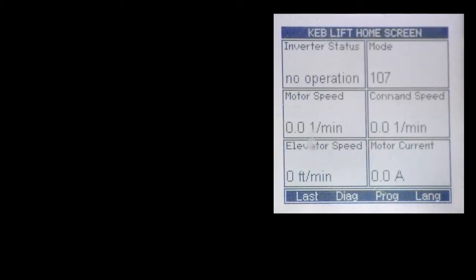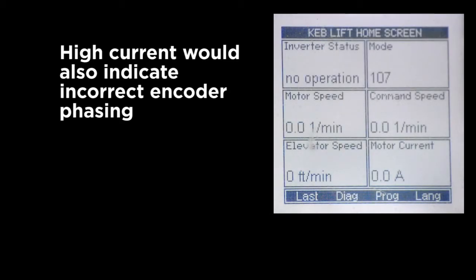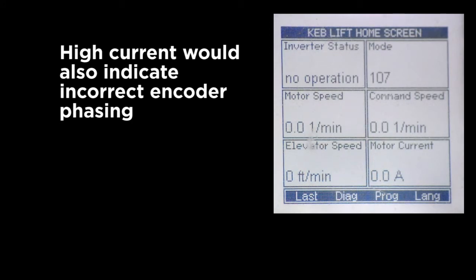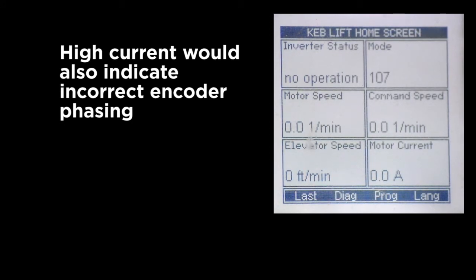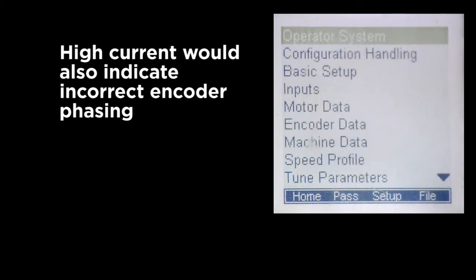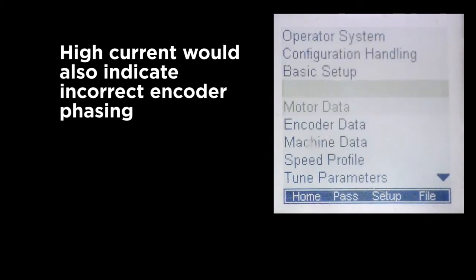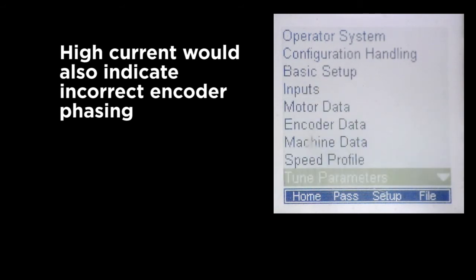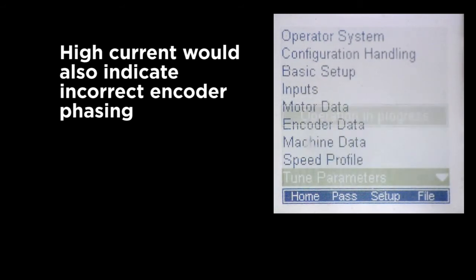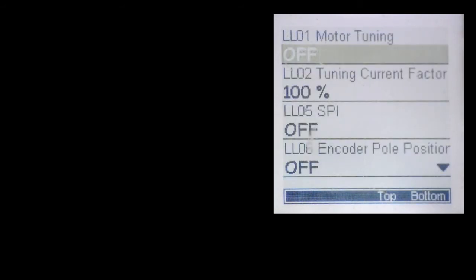In this case, we get a fault. You can also get high current. If the drive measures high current during this process, that may indicate that the encoder channels are incorrect.